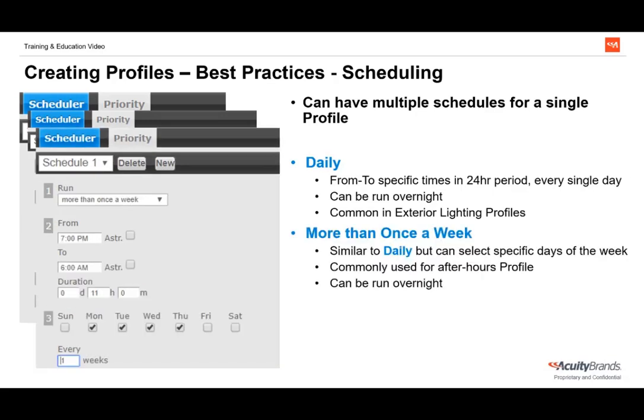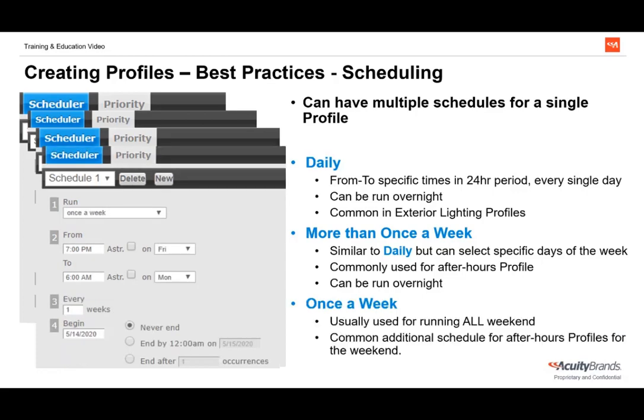More than once-a-week schedules are similar to daily schedules but allow specific days of the week to be selected. These are common for after-hours profiles in spaces unoccupied all weekend. For example, Monday through Thursday might be selected — not Friday — because a second once-a-week schedule handles Friday night through Monday morning. Once-a-week schedules are typically used for running profiles all weekend, since starting Friday and ending Monday is one long occurrence per week.